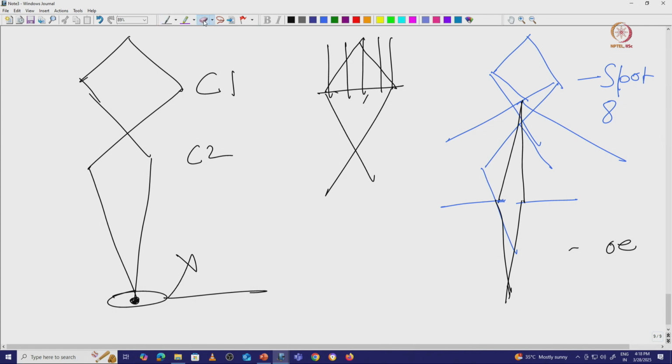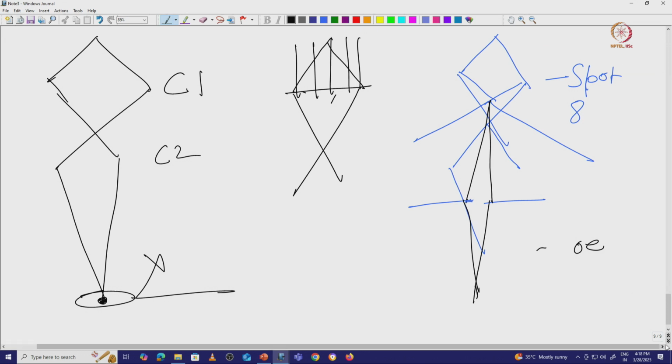That is the reason we have to play around with the lens current in such a way with the upper objective lens, so we can get the best possible electron dose as well as a parallel electron beam. How can we get that? If we come again, it will be better to draw the optical axis at the beginning. I am not talking about C1 or C2 changes, because we already discussed that.